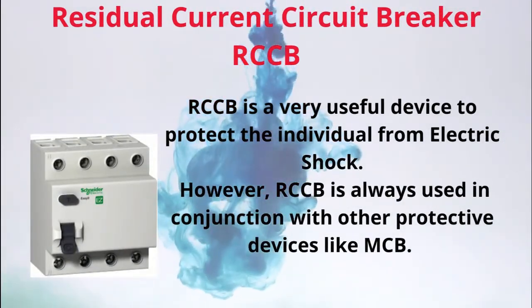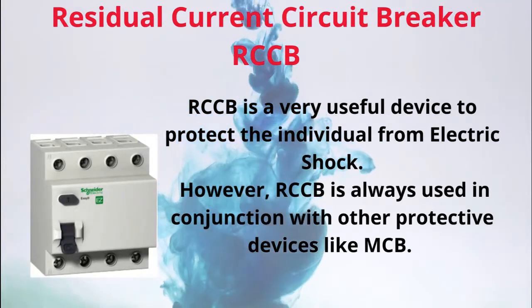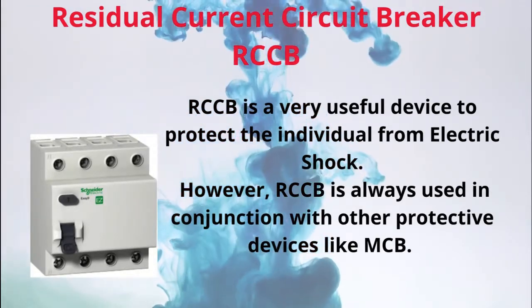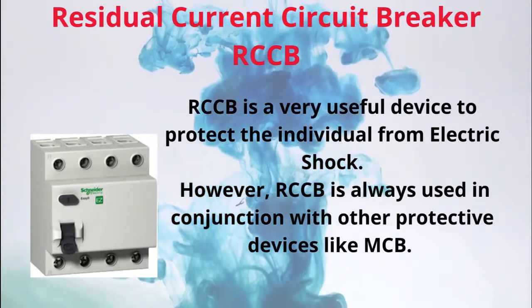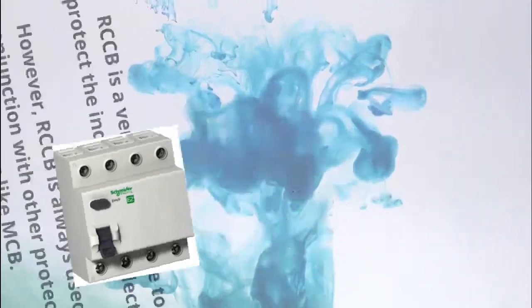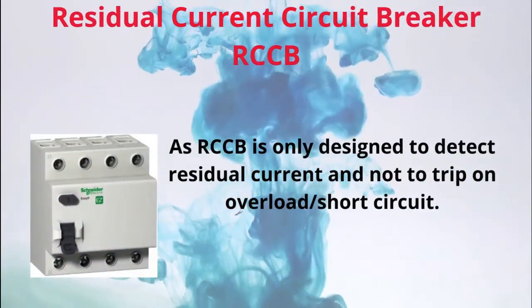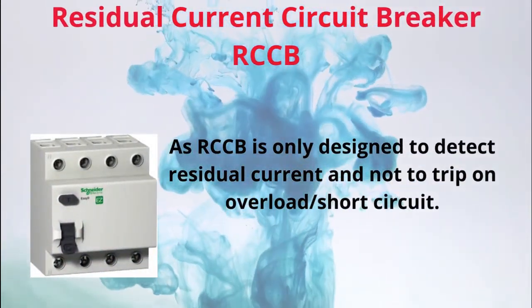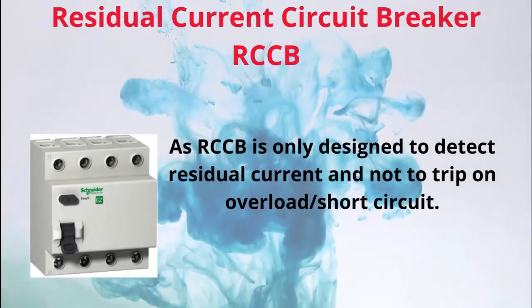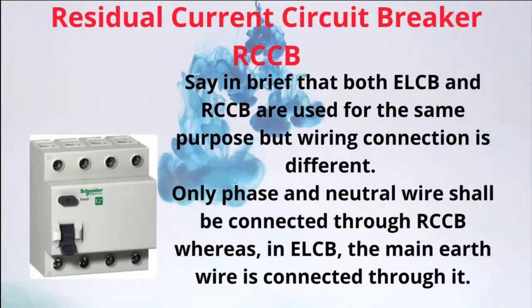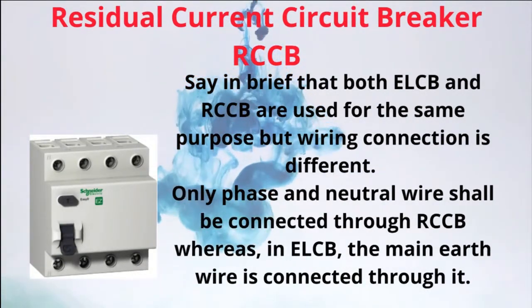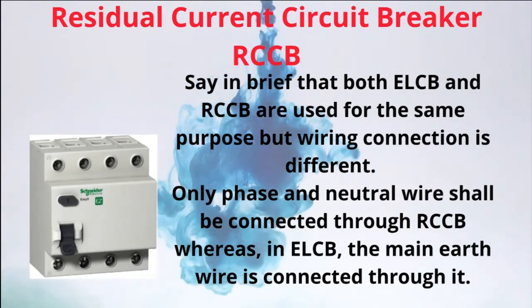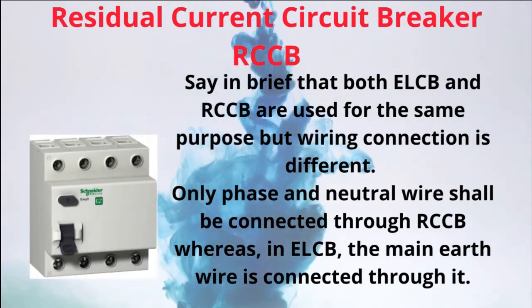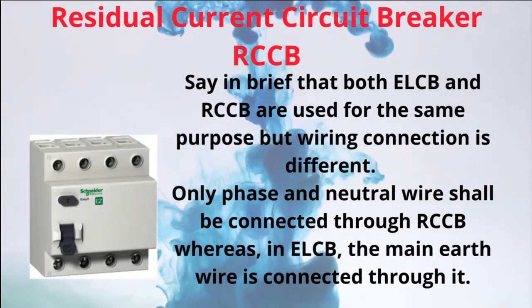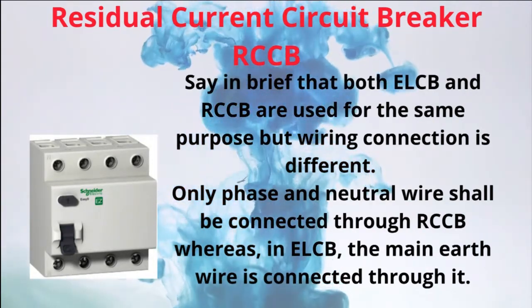RCCB is a very useful device to protect individuals from electric shock. However, RCCB is always used in conjunction with other protective devices like MCB, as RCCB is only designed to detect residual current and not to trip on overload or short circuit. In brief, both ELCB and RCCB are used for the same purpose but the wiring connection is different. Only the phase and neutral wires shall be connected through RCCB, whereas in ELCB, the main earth wire is connected through it.